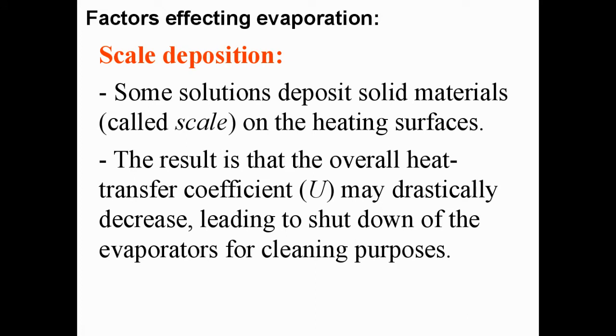Some solutions deposit solid materials called scale on the heating surface. This results in the overall heat transfer coefficient U drastically decreasing, leading to shutdown of the evaporator for cleaning purposes. Keeping scale or deposits on the surface means too much energy is needed, which is a waste of resources, money, and energy — meaning you need to clean the evaporator, replace it, or use a standby evaporator.